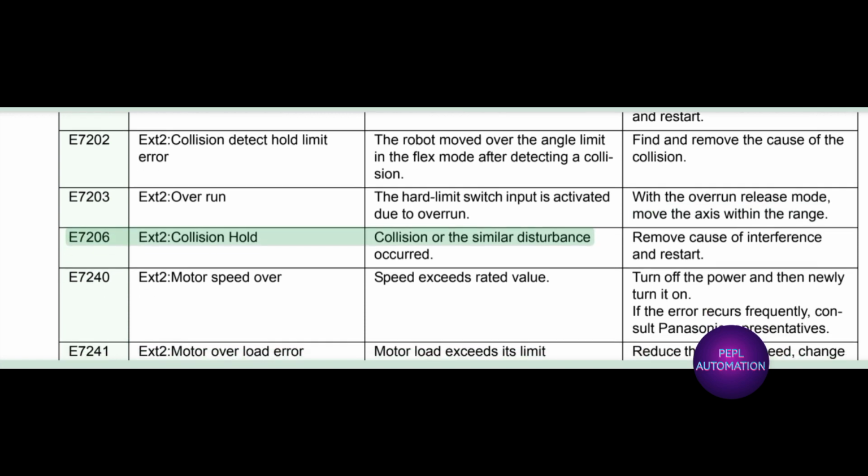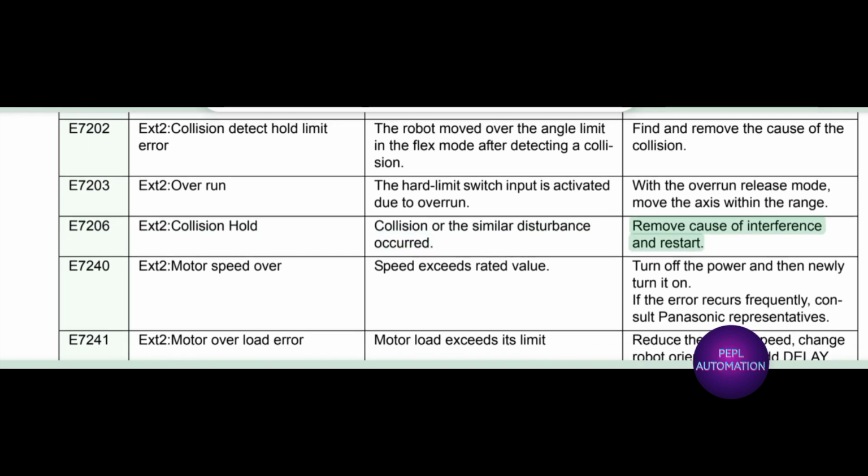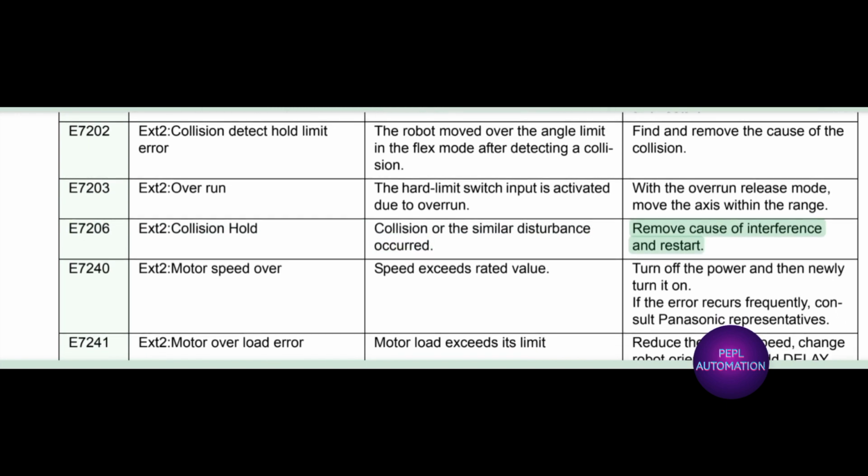E7206, Ext2: Collision Hold. Collision or a similar disturbance occurred. Remove cause of interference and restart.